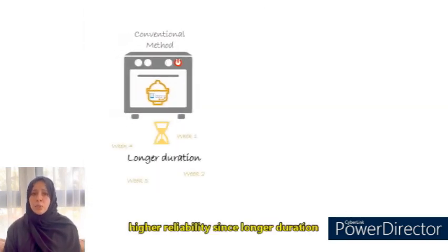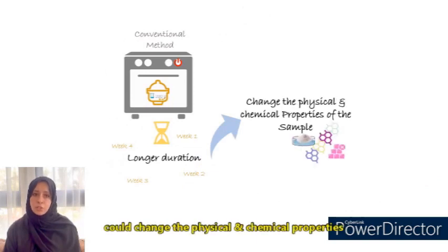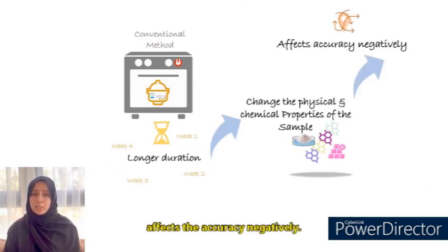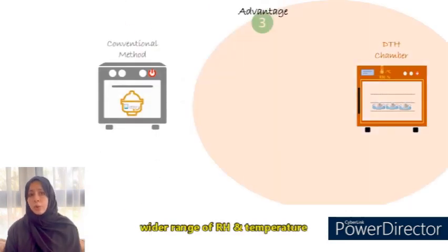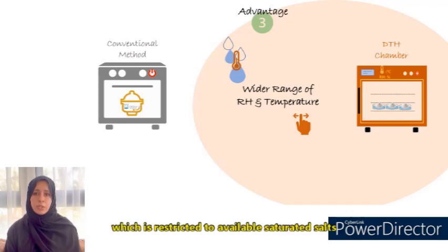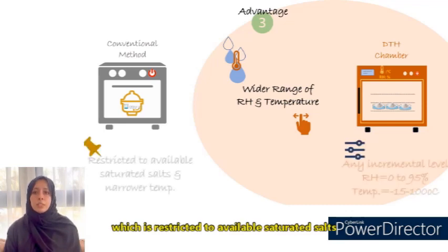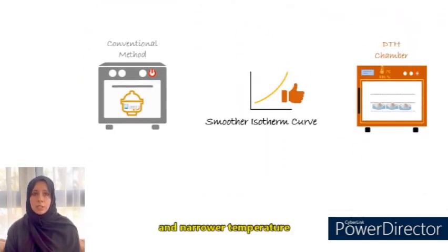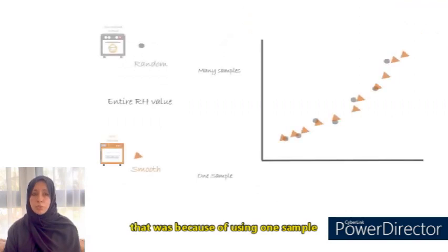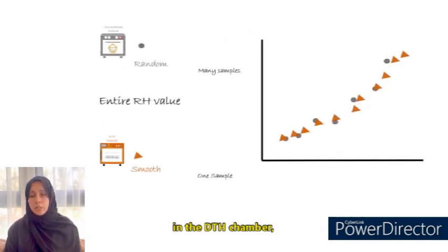Higher reliability, since the longer duration in the conventional method could change the physical and chemical properties of the sample, consequently affecting accuracy negatively. A wider range of relative humidity in the chamber, in contrast to the conventional method which is restricted to available saturated salts and narrower temperature. A smoother isotherm curve was observed with the new method, unlike the older one, because one sample is used for the entire range of relative humidity in the DTH chamber.